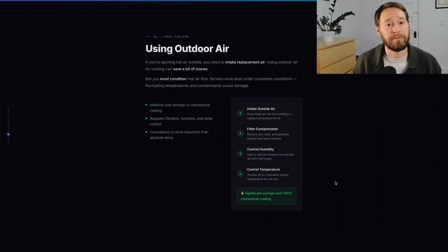You'll see computer hardware coming out of old crypto mining facilities doing this, and it's absolutely destroyed after 3 years because they're sucking in wet, dirty air that causes corrosion, with salt buildup on it. All of that reduces the usable life of your equipment and ultimately its resale value. So you're paying an accelerated depreciation schedule that might be faster than the money you're saving by not paying for proper air conditioning.